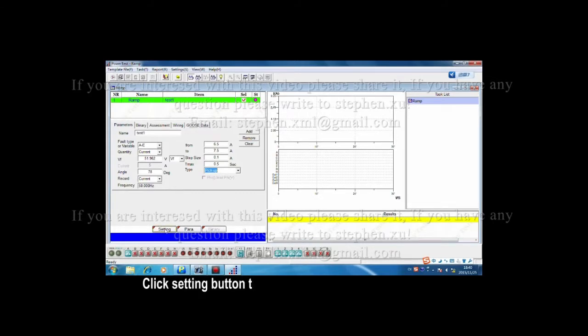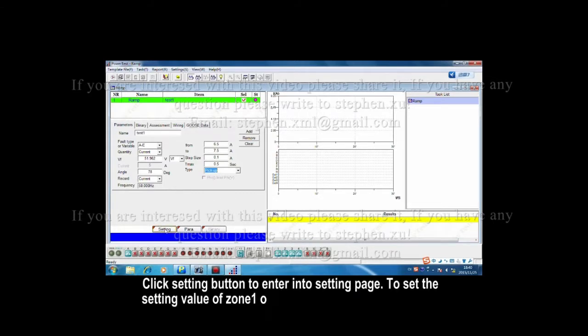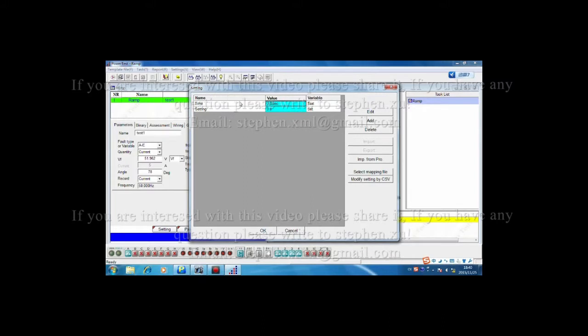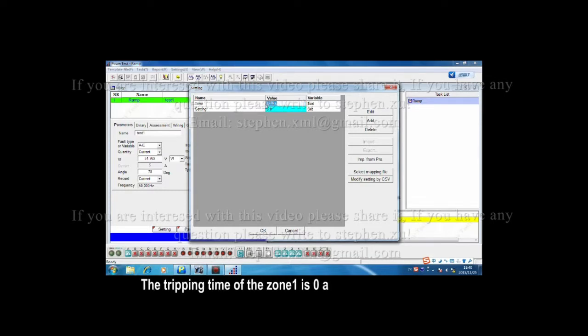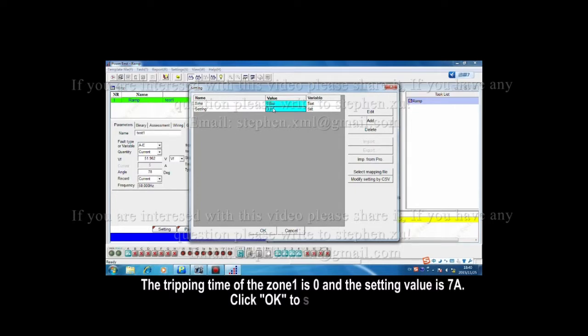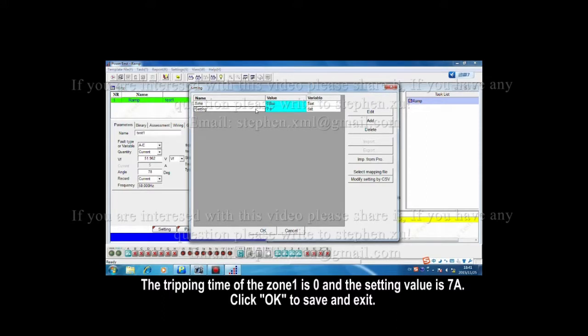Click setting button to enter into the setting page to set the setting value of zone 1 of residual grounding fault here. The tripping time of zone 1 is 0, and the setting value is 7 Ampere. Click OK to save and exit.